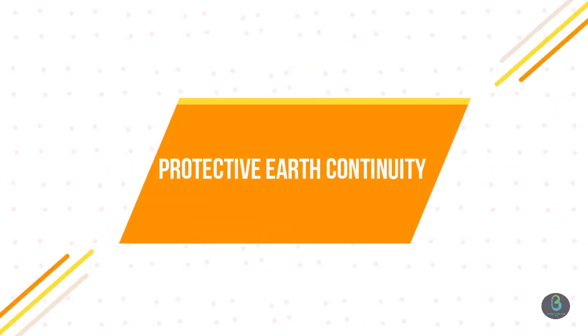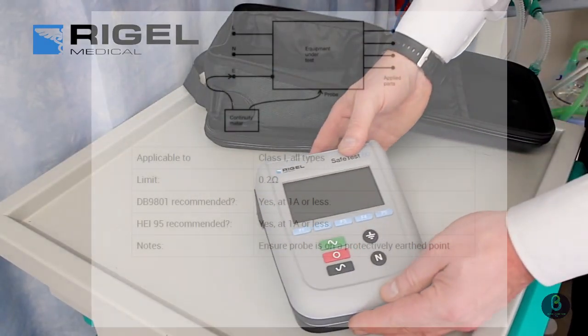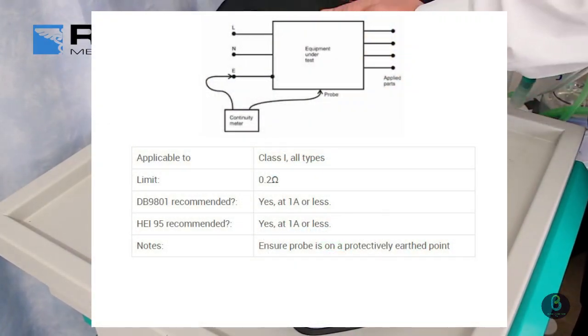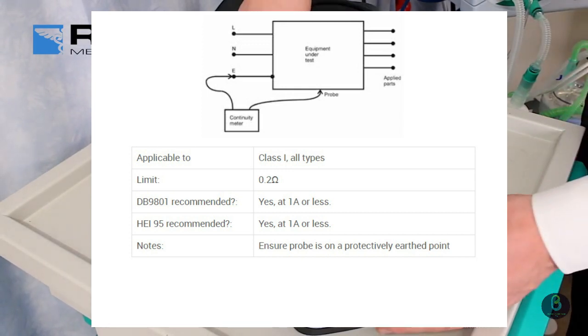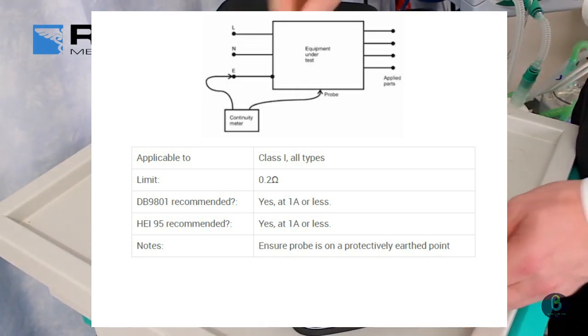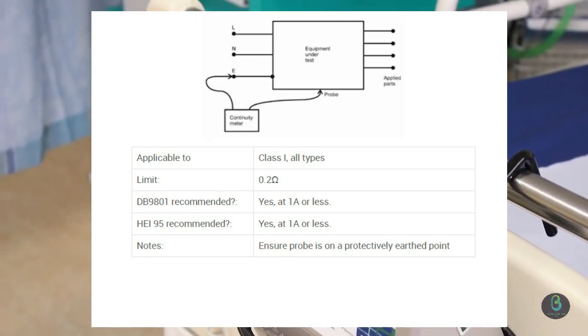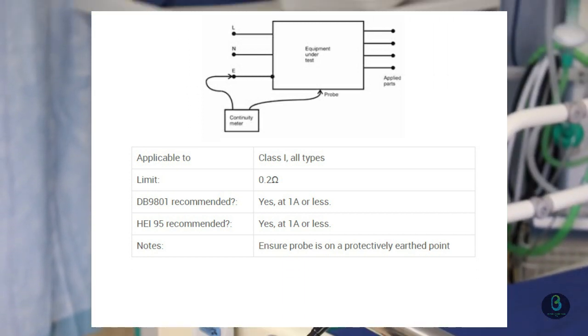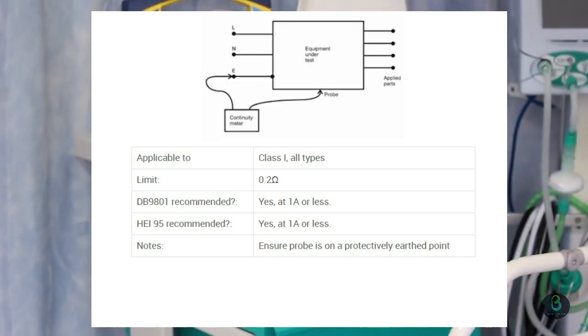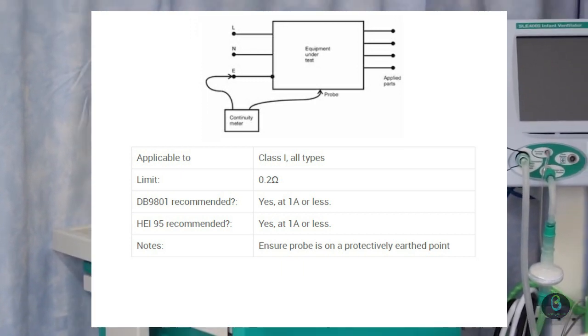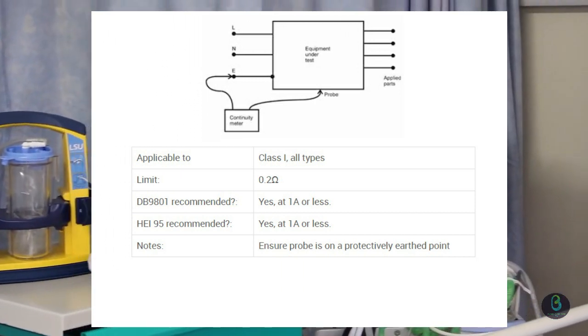Protective Earth Continuity. The resistance of the protective earth conductor is measured between the earth pin on the mains plug and a protectively earth point on the equipment enclosure. The reading should not normally exceed 0.2 ohms at any such point. The test is obviously only applicable to Class 1 equipment.